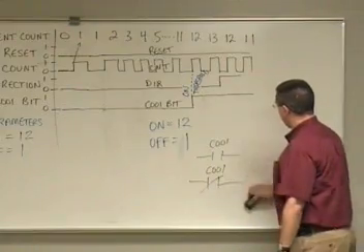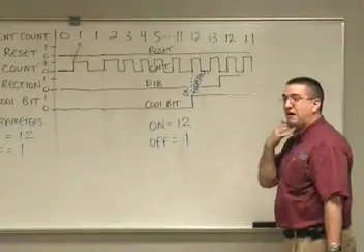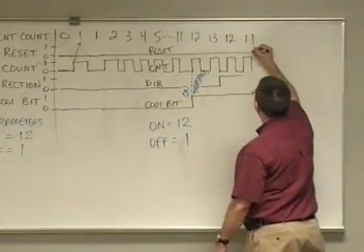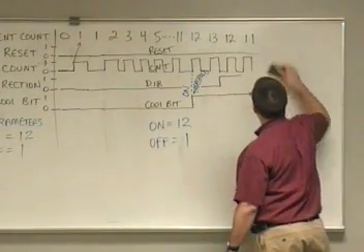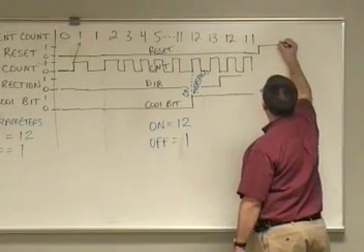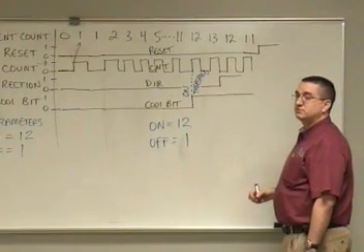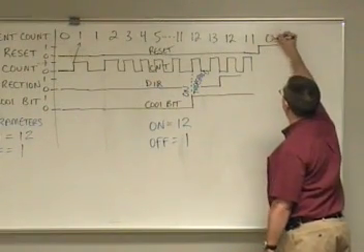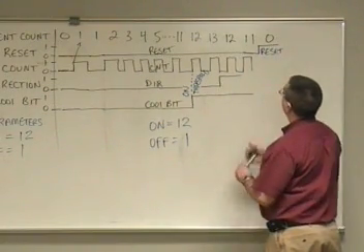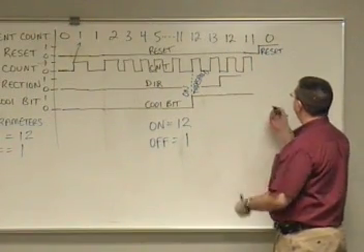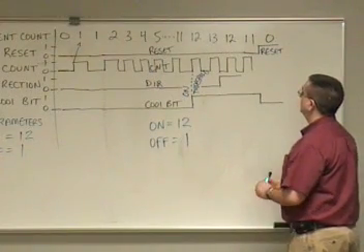All right. So we know that we're decrementing. We know that if we continued to decrement all the way down to 0, it would turn off, right? But let's do this instead. Let's take that reset pin. What if we make that reset pin high? What happens to my current value? Restarts at 0. Goes directly to 0. Because this would be my reset pin going high. As soon as my reset pin goes high, the C001 bit's going to do what? It's going to de-energize.